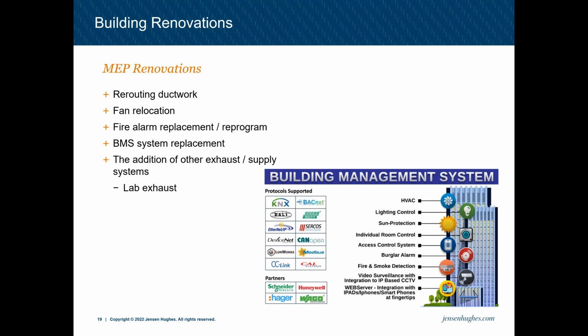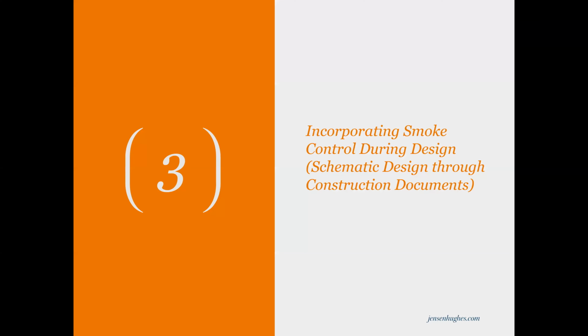And then the addition of other exhaust or supply systems, this tends to be with occupant changes. So if we go from an office to a lab building, and we have lab exhaust that has to run during a fire alarm event, and maybe this lab exhaust is open to our stairs, or can share the same corridor as our stairs, it's always worth consulting with whoever designed the system or your co-consultant who you're working with on this project, to make sure that these changes don't have an impact on our system's original design intent. I'm going to hand it back over to Arthur and start talking about the next phase.